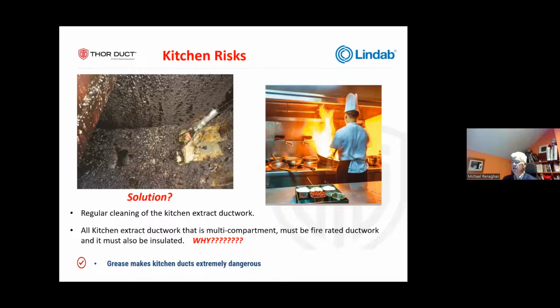So the regulation in DW 172 says that all kitchen extract ductwork that is multi-compartment, in other words, it travels across a number of compartments before it gets to outside, must be fire-rated ductwork, and it must also be insulated. By the way, a note to remember, it needs to be fire-resisting ductwork according to BS 9999 2017 from the back of the canopy all the way to atmosphere. So you can't have regular duct in the kitchen and fire duct the rest of the way. Fire duct is a full system, so it needs to be that way.